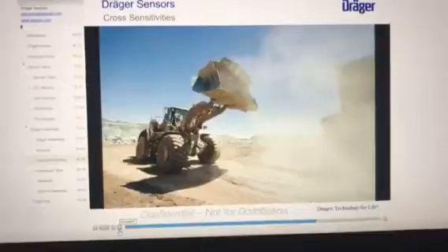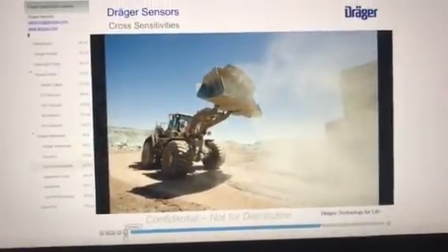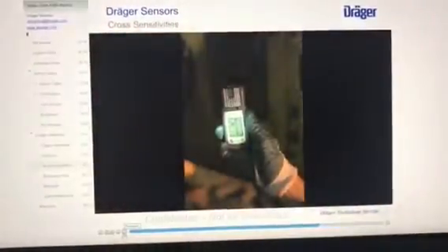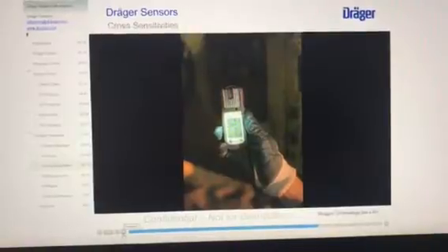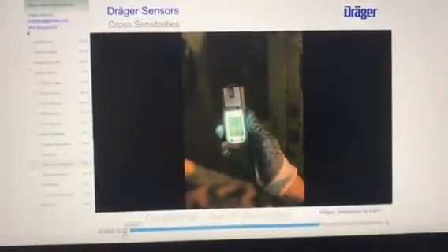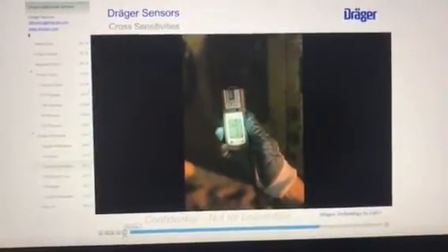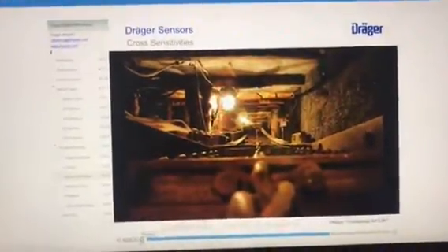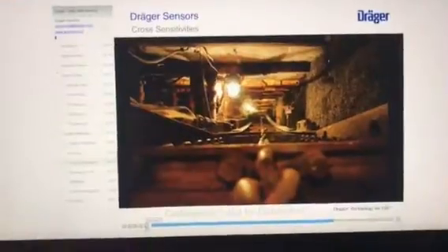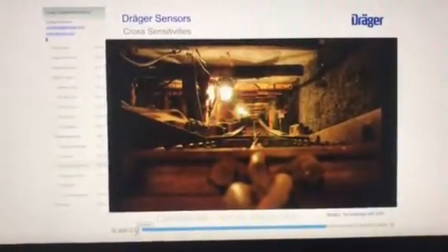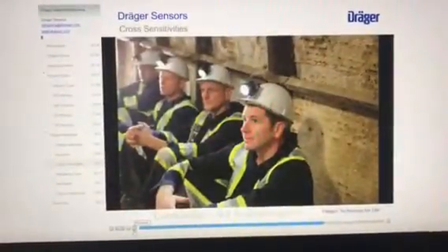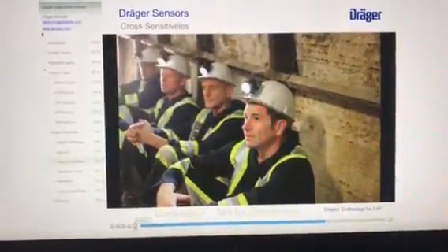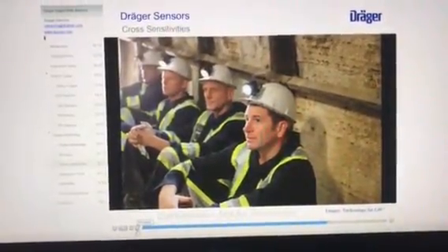The Draeger monitors worn by the mining company employees displayed a carbon monoxide level of 14 ppm, while the contractor's monitors supplied by a competitor were displaying 22 ppm. Since these levels were over the allowable limit of 20 ppm, the contractors began walking off the job. The mining company needed to find out which sensor reading was correct in order to not stall production.